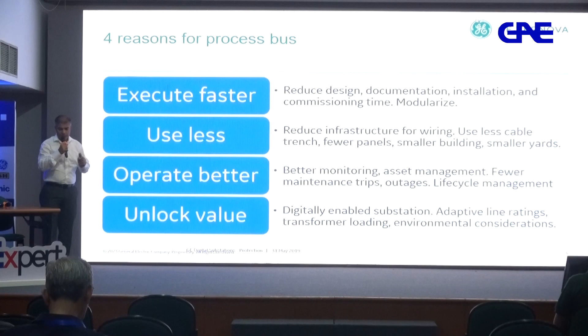Basically, there are four reasons for using process bus. One is to execute faster. If you are building a digital substation involving process bus, you should be able to execute faster. If you are spending the same time as a conventional substation, you're probably not taking advantage of what digital substation is capable of providing. You can also reduce design documentation. From the projects we have experienced so far, customers are able to reduce design drawings by about 90%. Previously, in a conventional substation, you used to produce 100 drawings; now you produce only 10. So design documentation has significantly reduced.